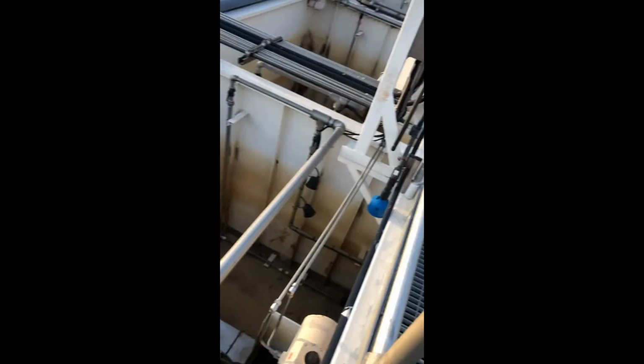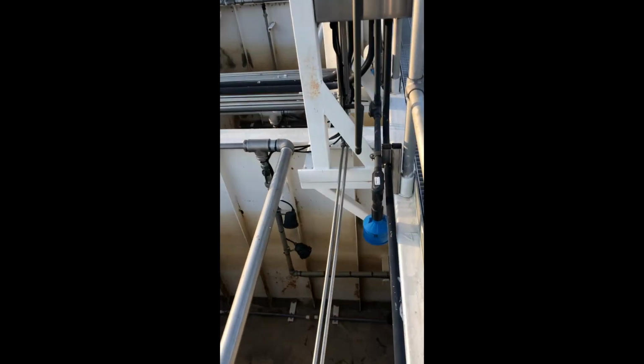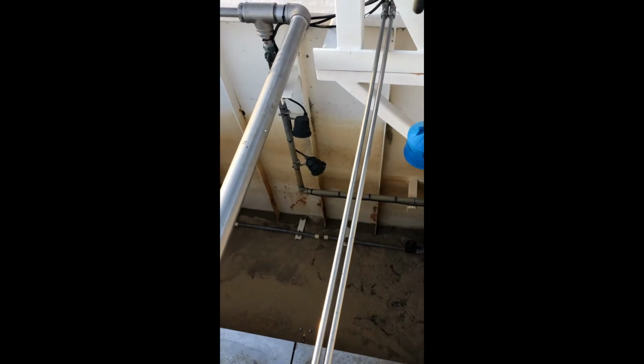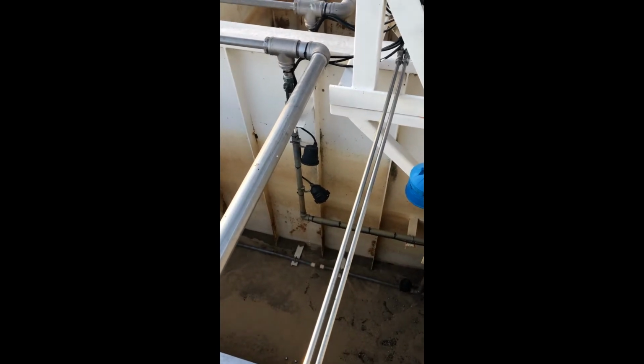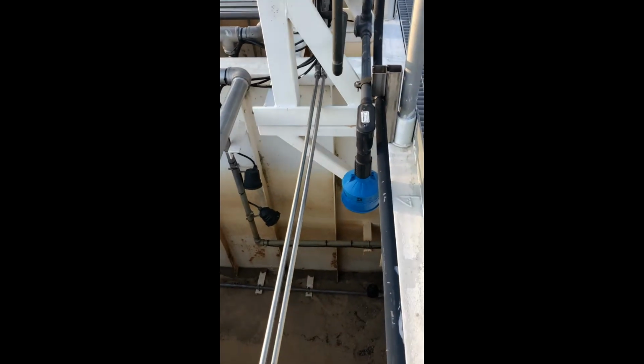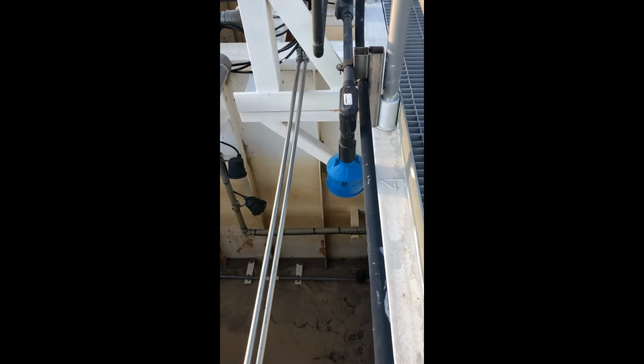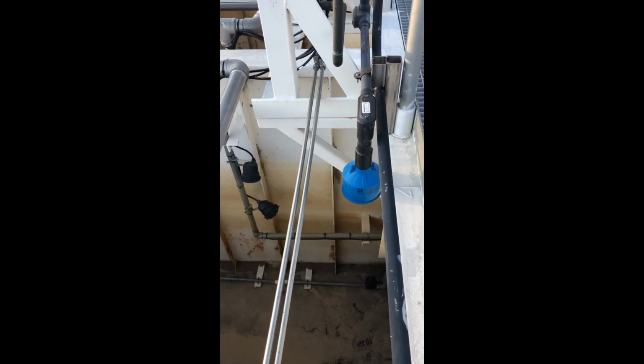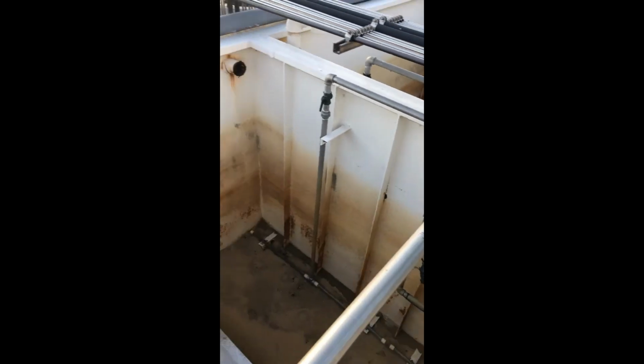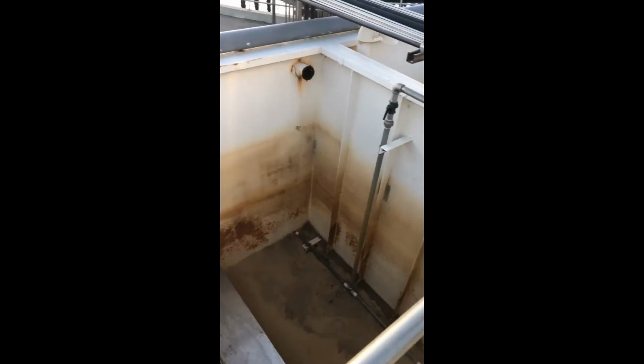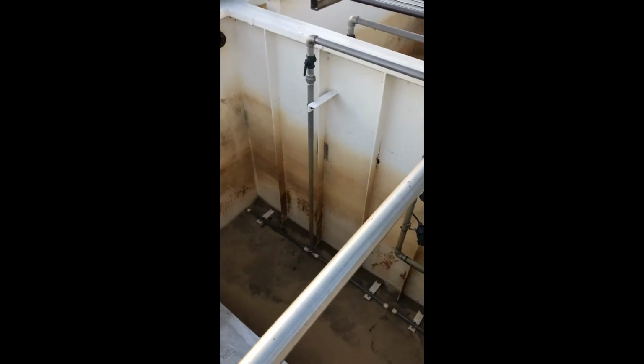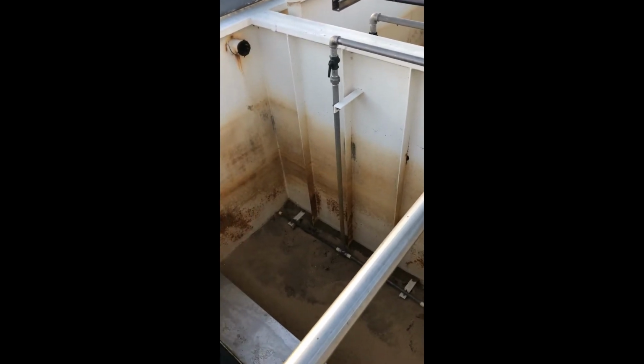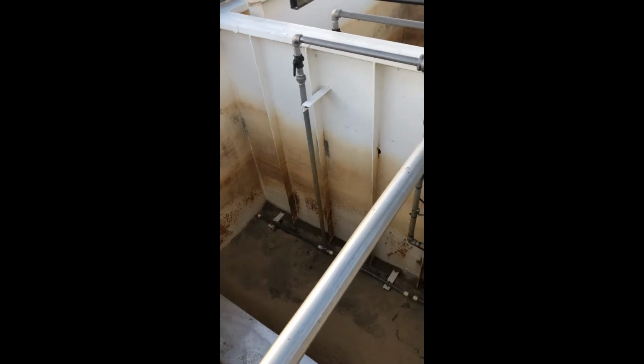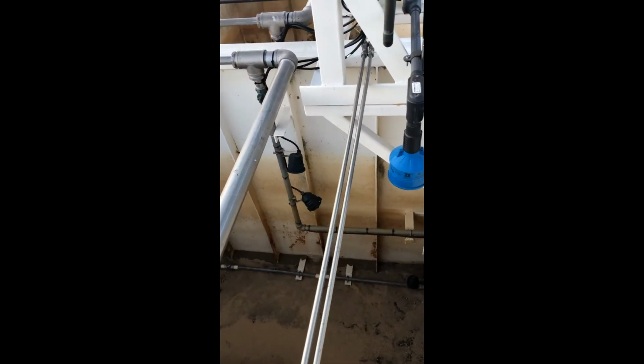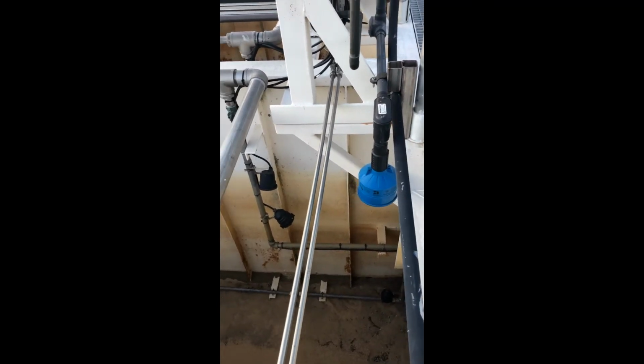the normal level is. You can see, it's kind of interesting, these black things down here are level sensors that we have in there, but they're actually not being used for anything. We found them to be quite unreliable, and so we ended up putting in an ultrasonic level sensor, which works great. And the nice thing about the ultrasonic level sensor is that we can change the backwash levels, the fill level, whatever levels we want. There's another level called the air scour level. That's when it's backwashing, how much water we want to be inside the tank when we do the air scour. And so this ultrasonic level controller does a much better job.